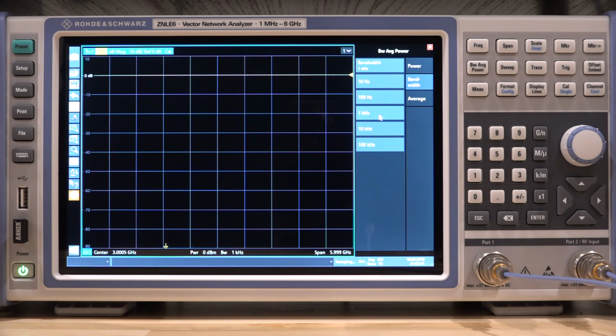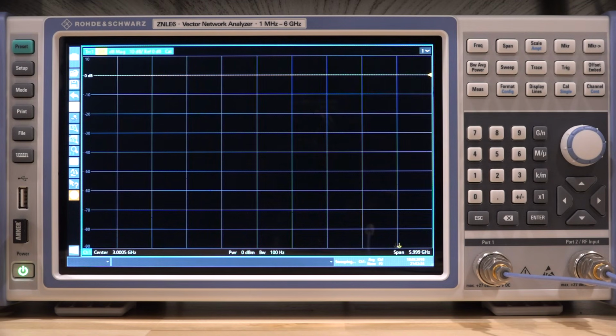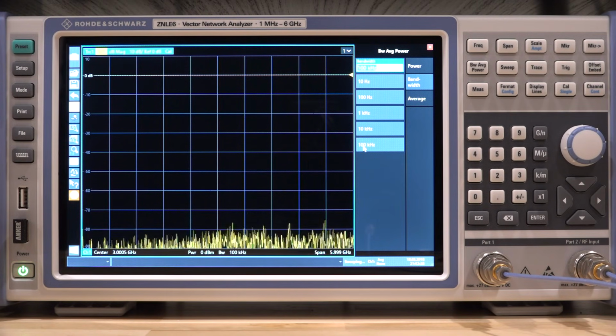So you can see at 1 kilohertz, again, we're doing port 1, port 2. If I go to 100 hertz, it sweeps much slower, of course, because it's using a much smaller IF bandwidth, but then it still jumps between the two ports. And as soon as I go to, let's say, something like, we lost that. Let's get that back here. If I go 100 kilohertz, you can see it sweeps exceptionally fast, and it doesn't even say. It probably doesn't have enough time to say which port is the stimulus. But either way, I prefer if this behavior was a little bit more consistent.